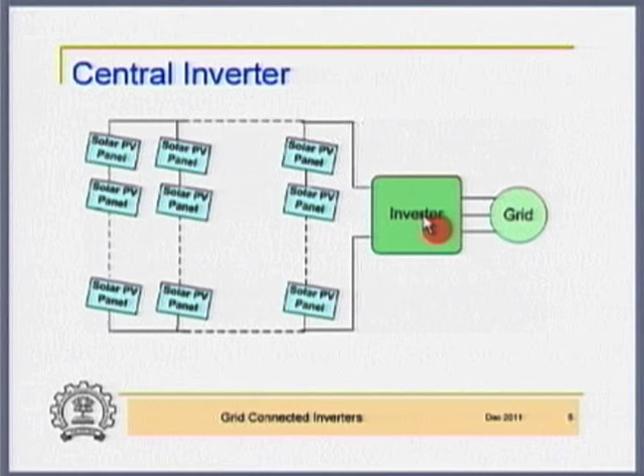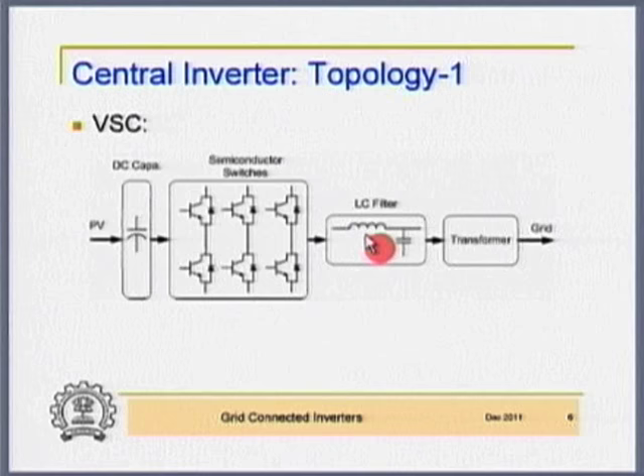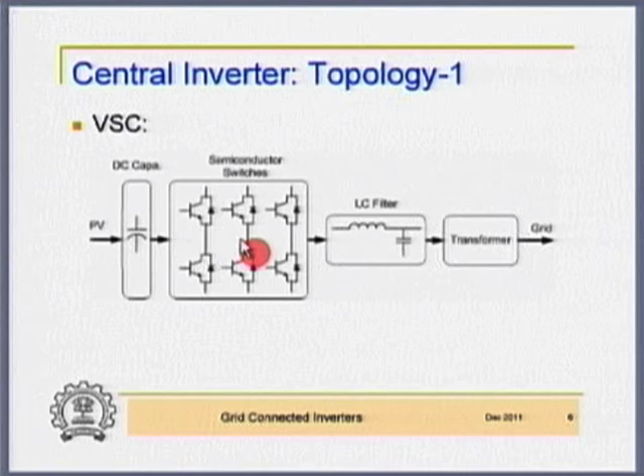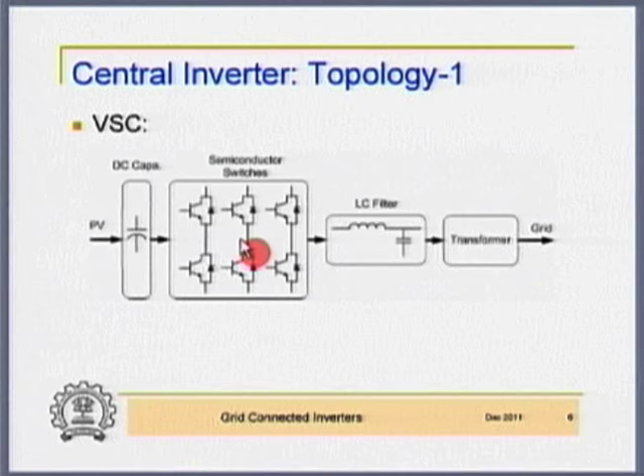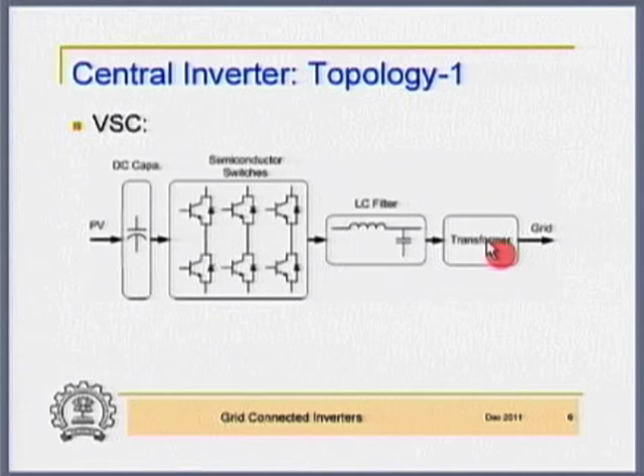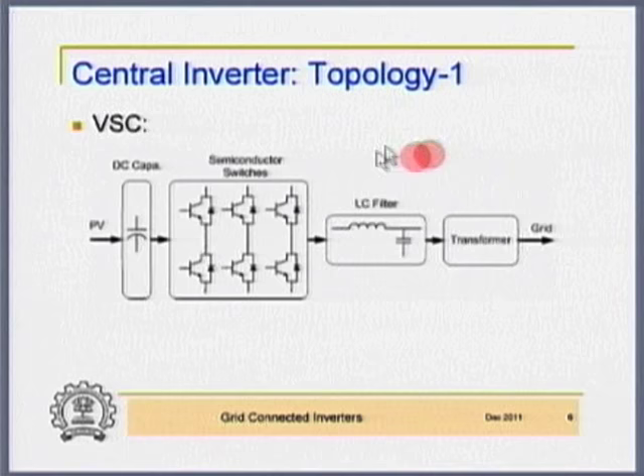This inverter could be either 2-level, 3-level, or a multilevel inverter. There is an LC filter to filter out high frequency components. As the power rating increases, you have to reduce the switching frequency. When you reduce the switching frequency, the frequency of the predominant harmonic in the output voltage also comes down, and that has to be filtered out using an LC filter. In addition, there is a transformer with leakage inductance, so it forms an LCL filter.